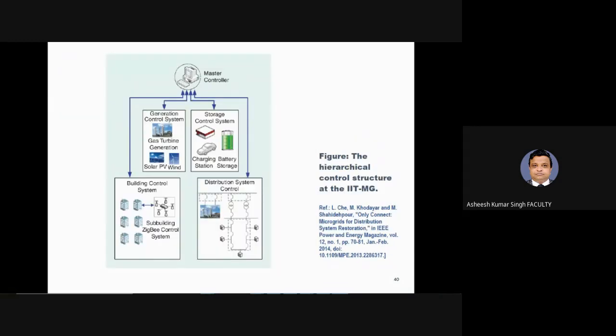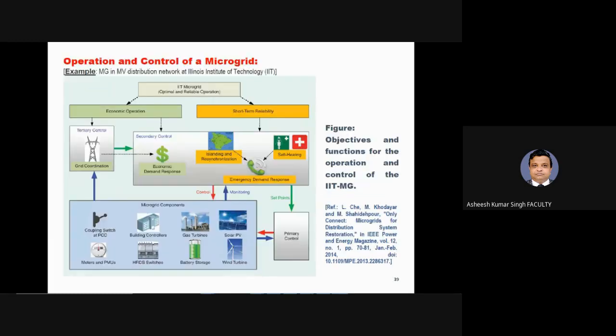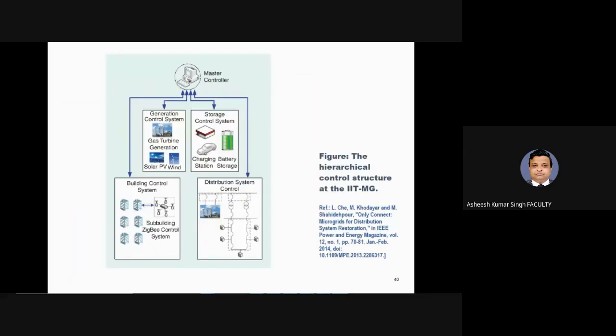And then comes the hierarchical control structure of this particular grid. Functionally, this is a 3-level hierarchical control as shown in the previous diagram. Primary, secondary, and tertiary control levels are considered here. At the primary control level, it is based on the droop characteristics of DERs for sharing the microgrid. Then comes the secondary control, which performs corrective actions to mitigate frequency and voltage errors introduced by droop control.